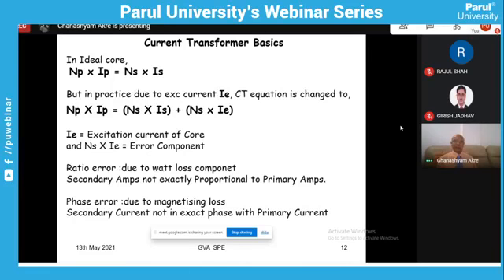Why are the errors important? In current transformer, if we are dropping the voltages, for a simple example of 66 kV to 110 volt, the ratio will be 600. Similarly, if you are connecting it to the current transformers of 100 by 1, the ratio will be 100. So if both the voltage coil and the current coil are connected to the measurement meter, then their multiplying factor will be 100 multiplied by 600, so 60,000. So here in this case, the error in the secondary measurement will amplify to 60,000 times. And that is why the accuracy of this current transformer has to be very, very high. And this is how it is actually recognized.